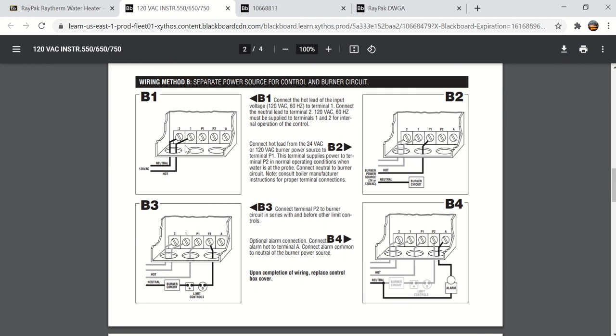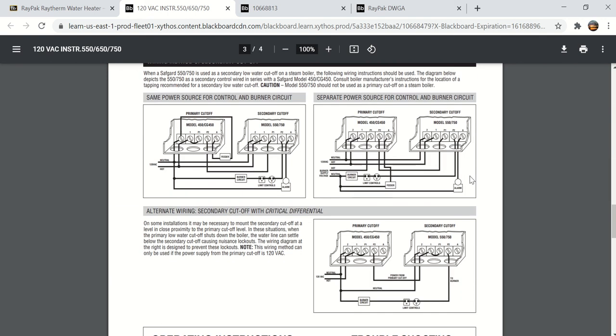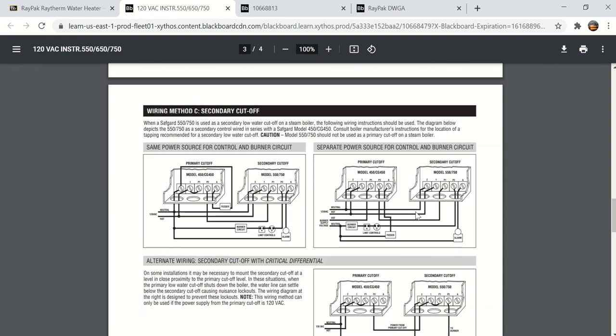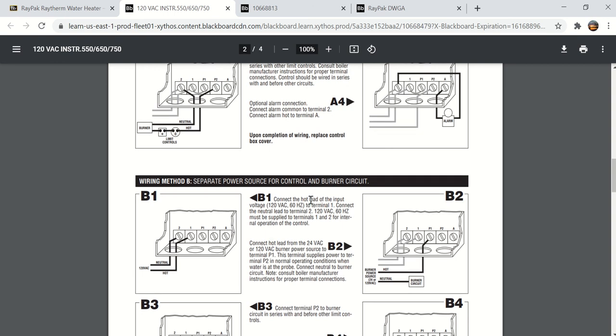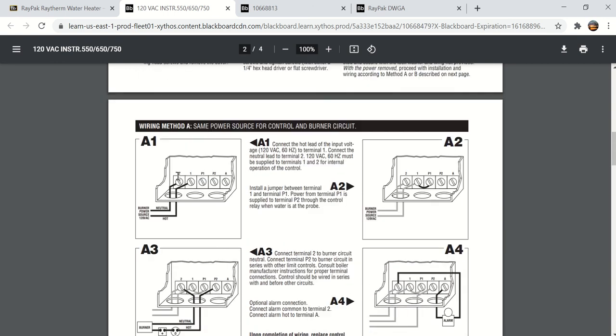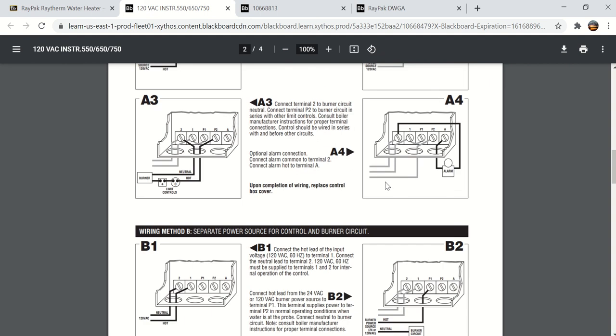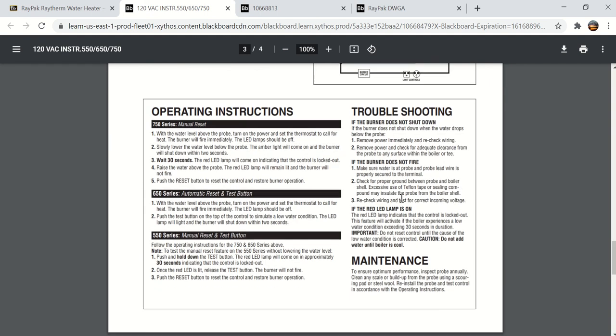And method B, you use a separate power source. So here's your 120 volt power to power the electronics in the low water cutoff, but here you use a separate circuit for the P1 and P2, and I don't know that it even has to be the same voltage, because you're just isolating, you're using just the P1 to P2 contacts. So the 2 different methods are actually, here's the third method, but the difference between method A and B is whether you use the same power for 1 to power P1, or you use a separate power to P1.